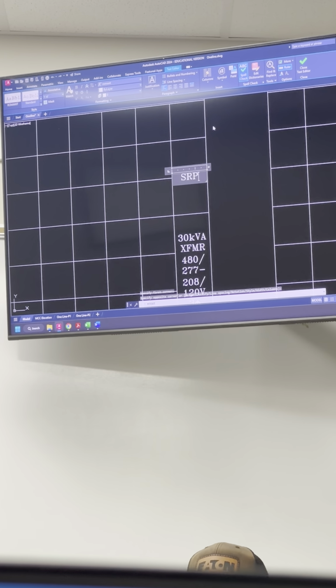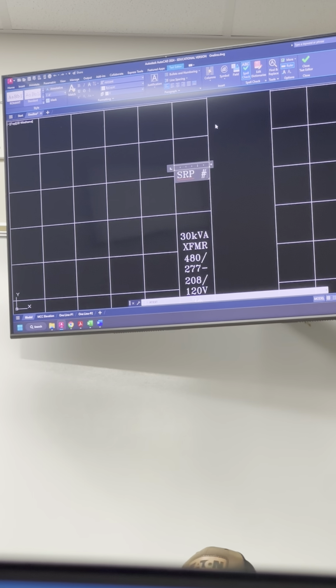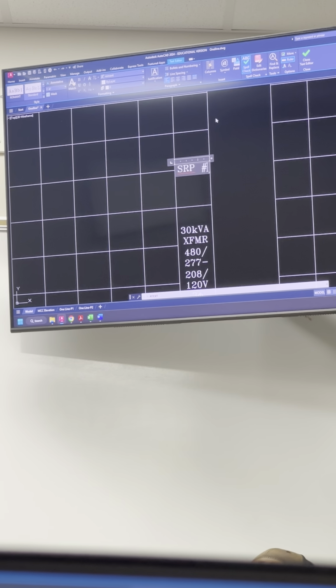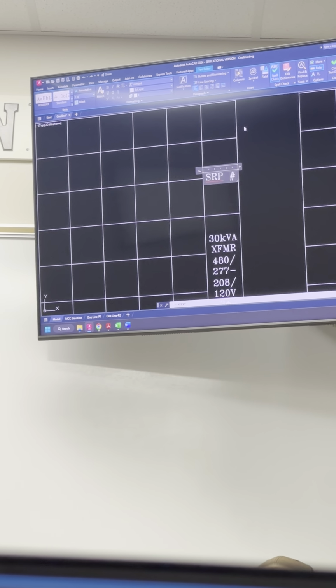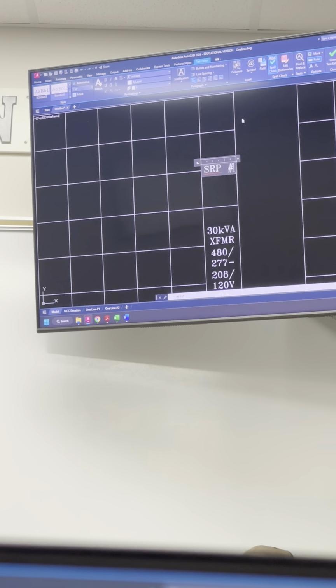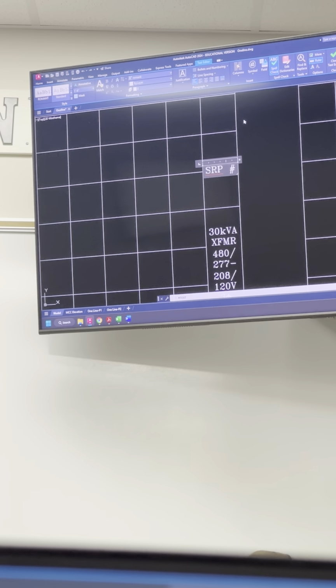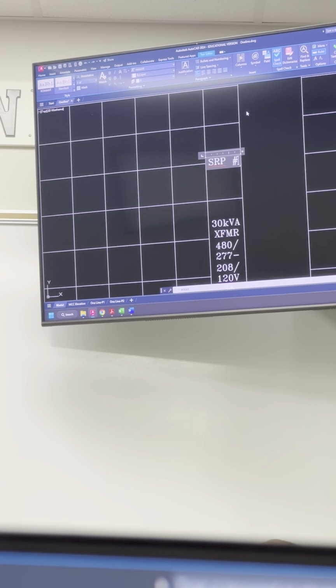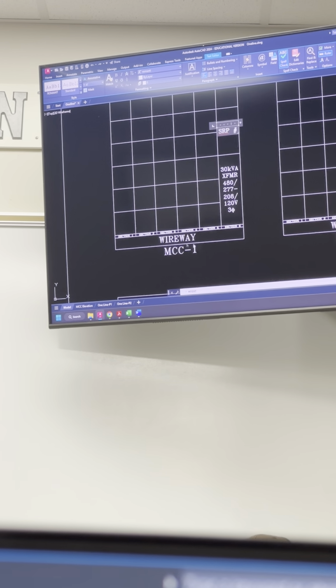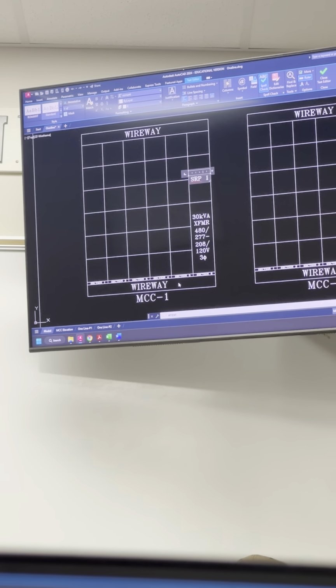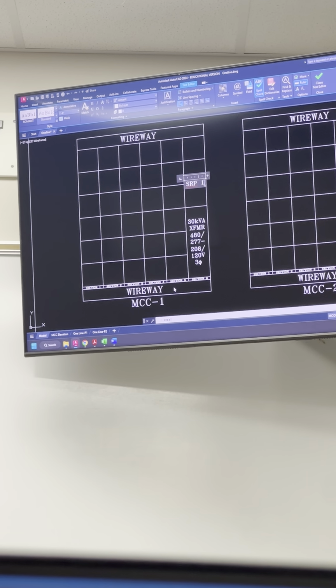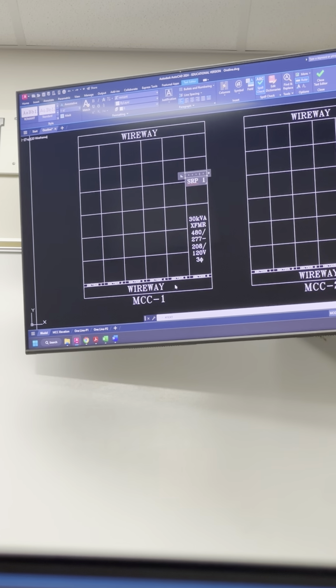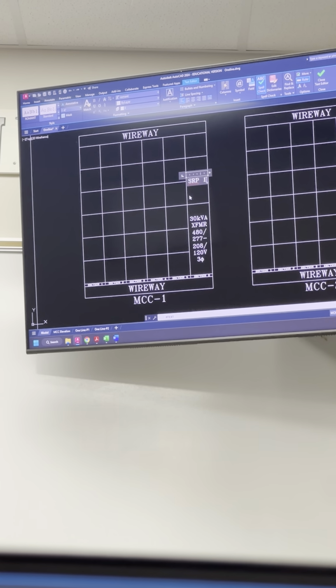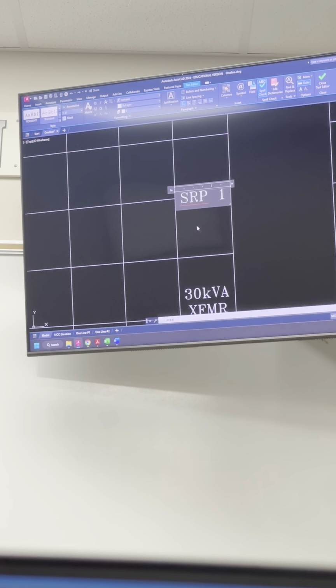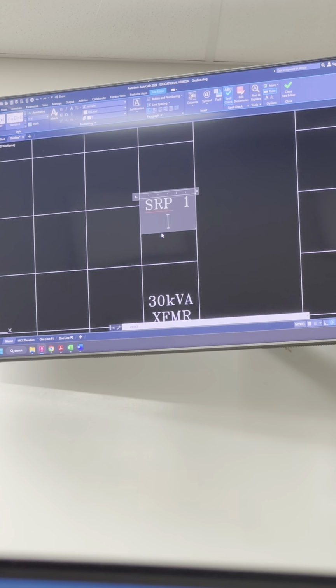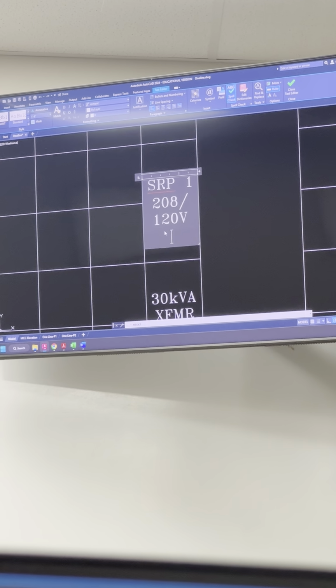We'll call this our shop receptacle panel, and put a number there—but you don't want to just call it shop receptacle panel, because you'll put this in every single MCC section 6. If you had 6 panels all called shop receptacle panel, that would be confusing. Since I'm in MCC 1, it makes sense to label this shop receptacle panel 1, and in MCC 2 it would be shop receptacle panel 2, and so on. We'll identify those panels and list the voltage present in them: this panel has 208, 120 in it, and that is 3-phase.